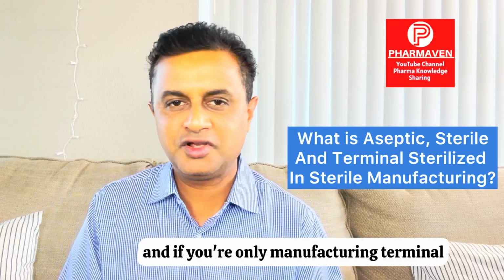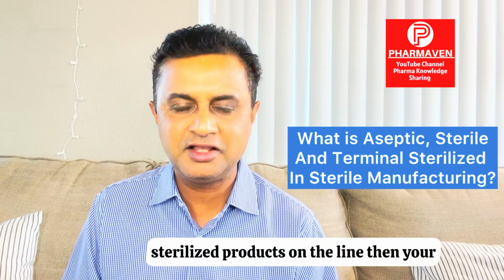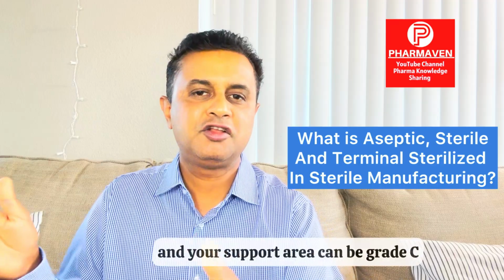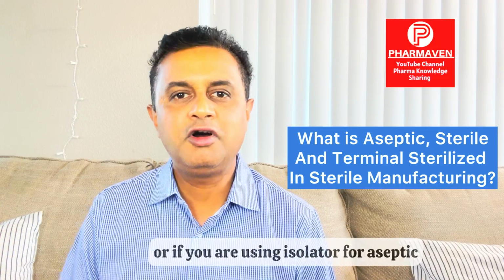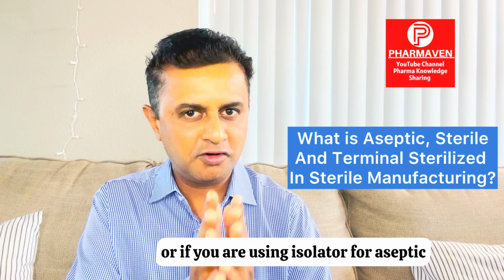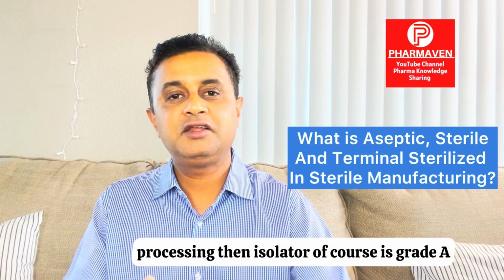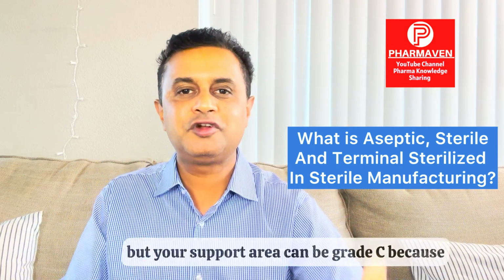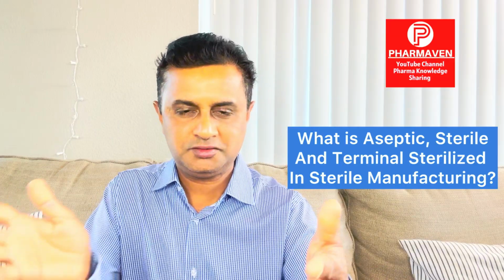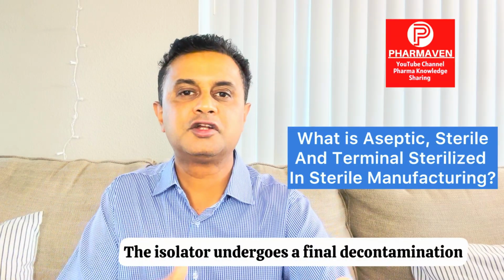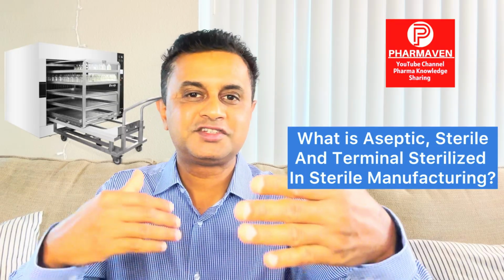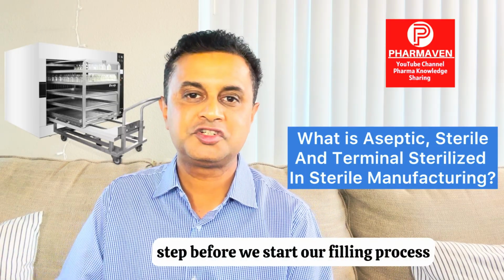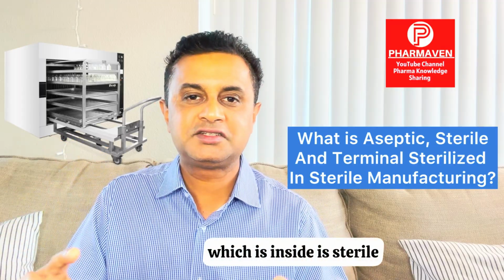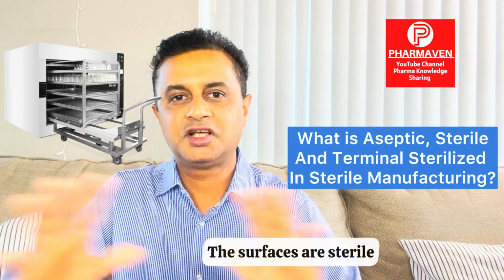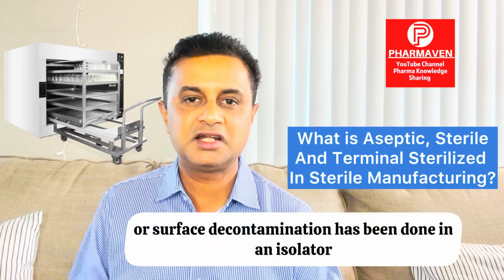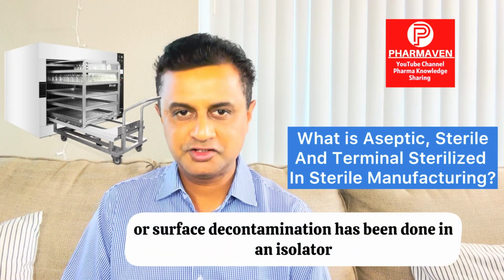And if you're only manufacturing terminal sterilized products on the line, then your filling line can be Grade A and your support area can be Grade C. Or if you're using an isolator for aseptic processing, the isolator is of course Grade A, but your support area can be Grade C because the isolator undergoes a final decontamination step before we start filling, to make sure everything inside is sterile - the surfaces are sterile, surface decontamination has been done in the isolator.